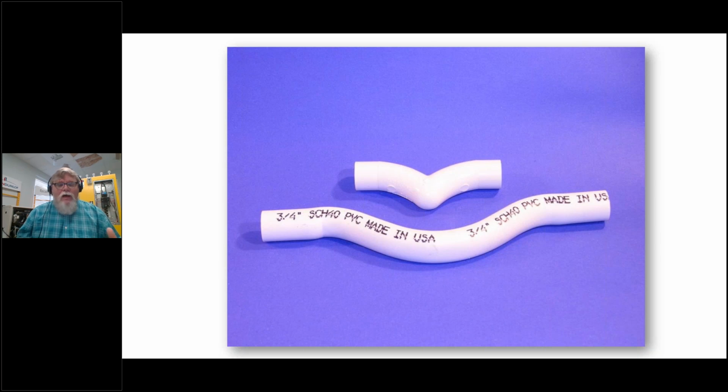Now, when I see the running trap, and I mentioned it a minute ago, I don't necessarily write it up if everything seems to be working properly, because I really don't know what the static pressure and everything is in the duct system. So I don't know if it's working well or not. There's just no way for me to tell by looking, unless it's actually cranking right then on a hot summer day.